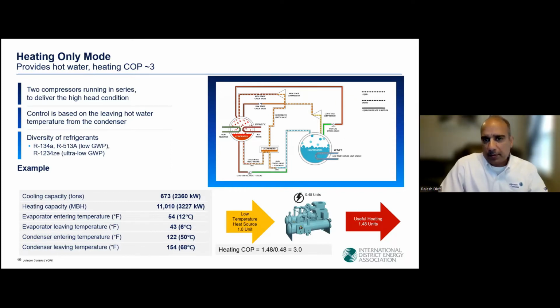The control is obviously based on the leaving hot water temperature. And in this particular example, the one listed on the bottom left of the slide, the source is actually city's wastewater at 43 F or 6 Celsius. And the sink is 154 F or 68 C, which is used for district heating of a large metro city.